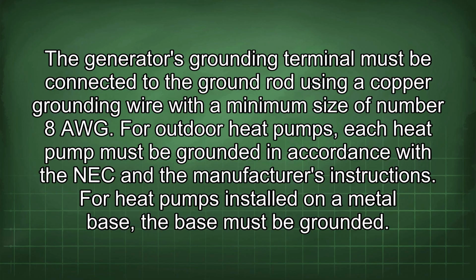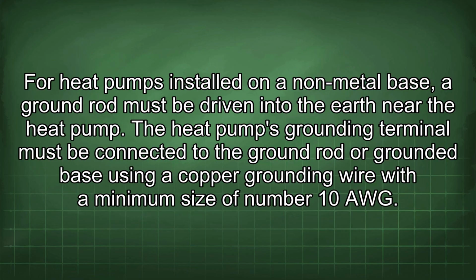of number 8 AWG. For outdoor heat pumps, each heat pump must be grounded in accordance with the NEC and the manufacturer's instructions. For heat pumps installed on a metal base, the base must be grounded. For heat pumps installed on a non-metal base, a ground rod must be driven into the earth near the heat pump. The heat pump's grounding terminal must be connected to the ground rod or grounded base using a copper grounding wire with a minimum size of number 10 AWG.